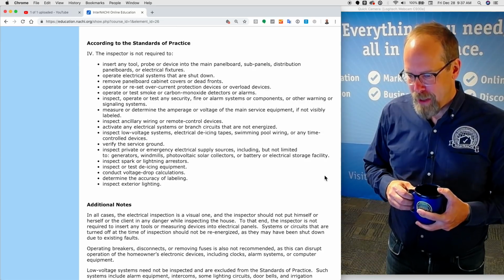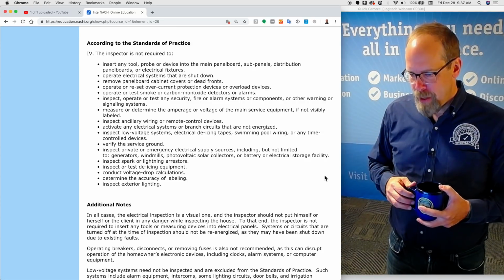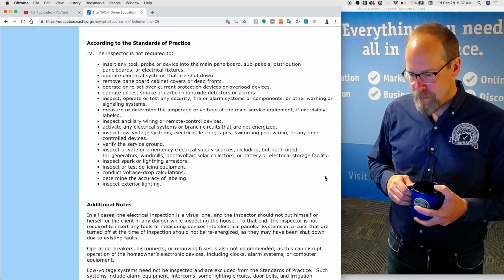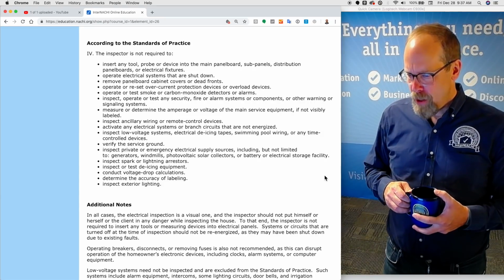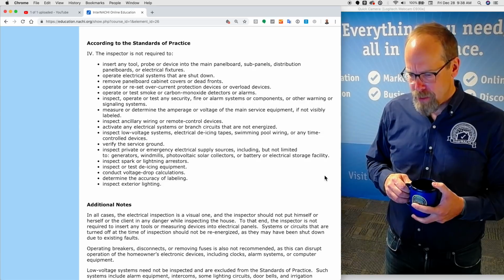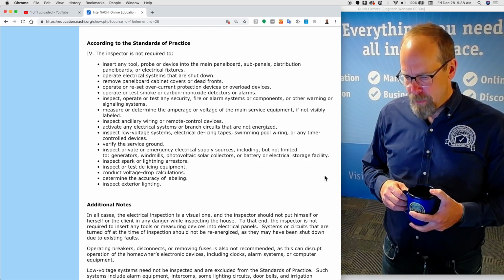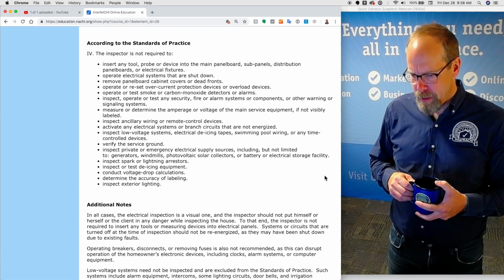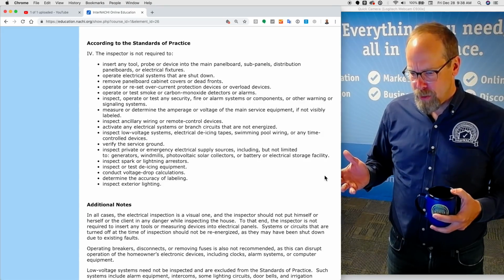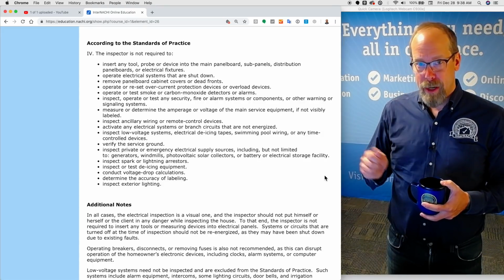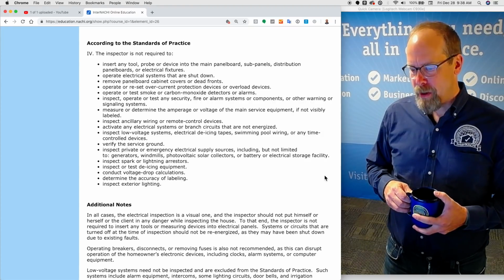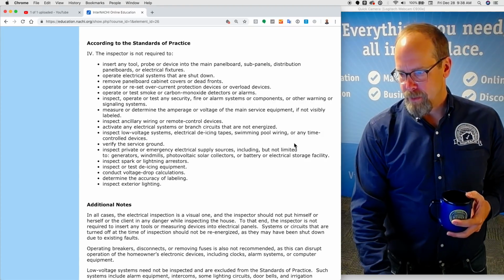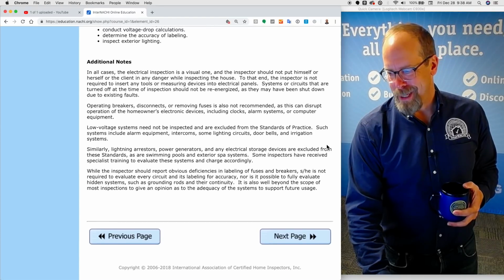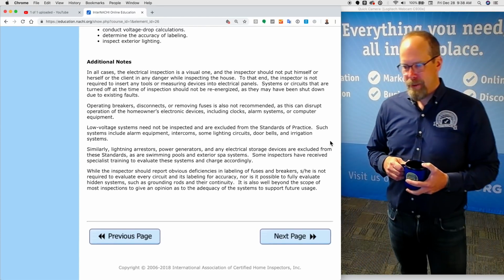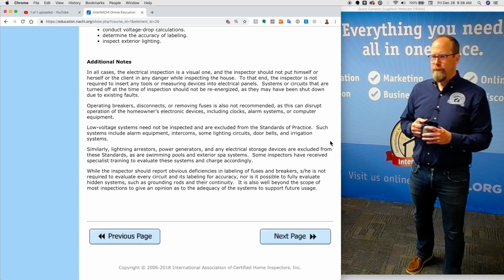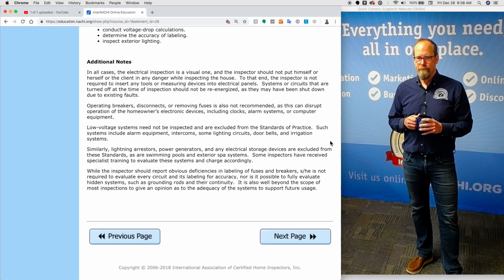The inspector is not required to verify the service ground, or inspect private or emergency electrical supply sources like windmills or solar panels. You're not required to inspect spark or lightning arresters, or inspect or test de-icing equipment. You're not required to conduct voltage drop calculations. You're not required to determine the accuracy of labeling. All the breakers should be specifically labeled. You're not required to inspect exterior lighting. I tend to inspect the front lamp if it's out there, and certainly not any decorative lighting or landscaping lighting.